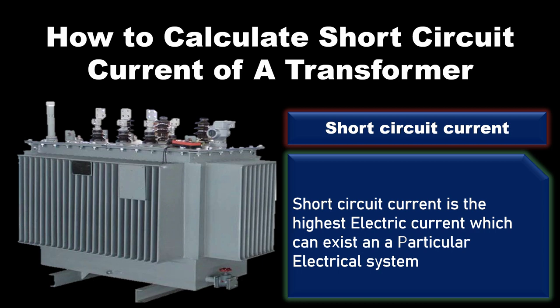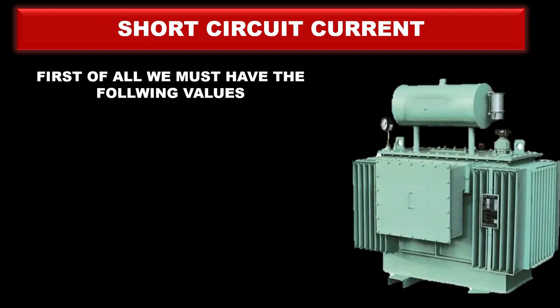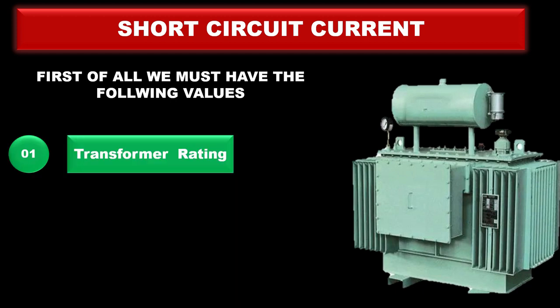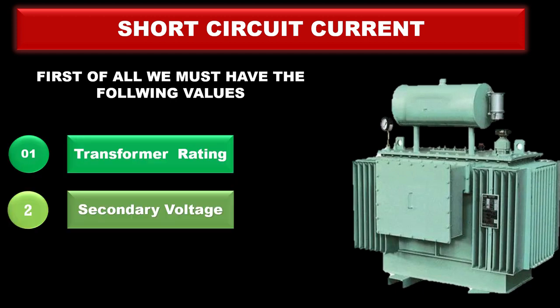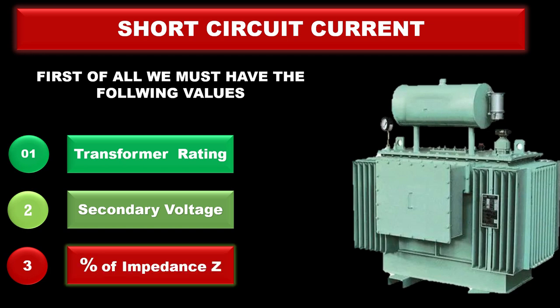Now how to calculate short circuit current? To calculate short circuit current, first we must know these three values: transformer rating, transformer secondary voltage, and the impedance of the transformer. Impedance of a transformer is always mentioned in the transformer name plates.